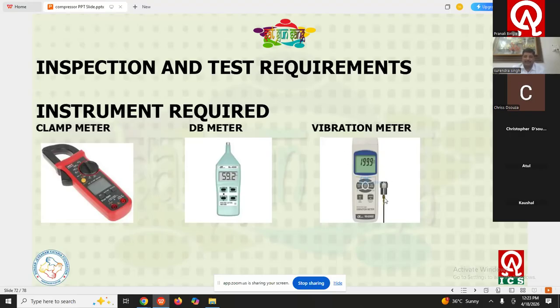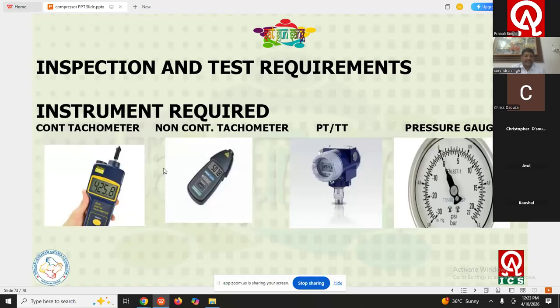This is the vibration meter. This probe you need to locate at the measuring surface where you are going to take the readings. The probe automatically shows the vibration level on the display. This vibration meter also has two modes. You select the mode, either to take the vibration reading in mm per second or in micron value. This is the tachometer. We use a tachometer for the measurement of RPM, and tachometers are further categorized into types. One is contact type, and the other is non-contact.